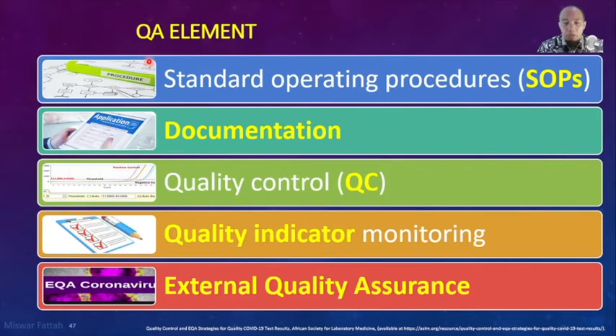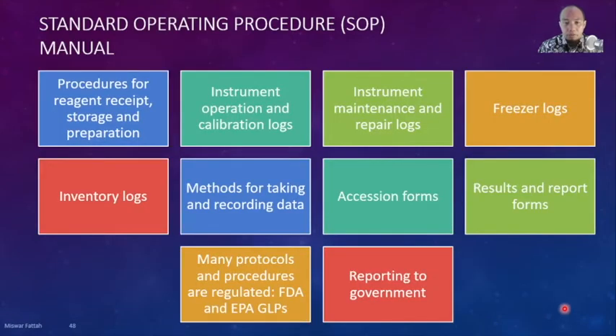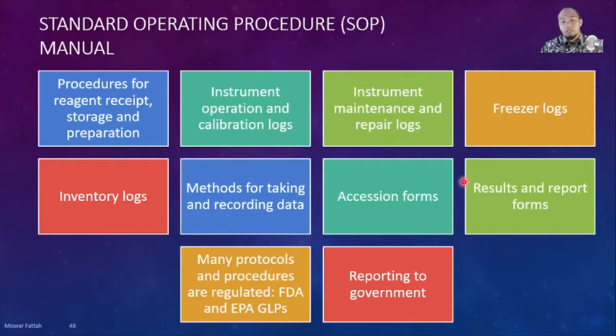Quality assurance elements include standard operating procedures, documentation, quality control, quality indicator monitoring, and external quality assurance. Standard operating procedures should include a manual of procedures for reagent receipt, storage and preparation, instrument operation and calibration log, instrument maintenance and repair log, freezer log, inventory log, methods for taking and recording data, accession forms, and result and report forms. Many protocols and procedures are regulated by FDA, and we need to report to government.